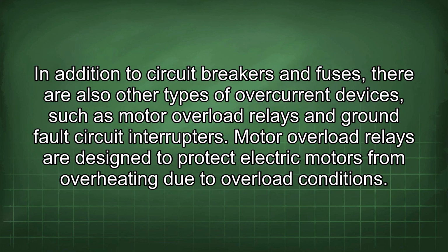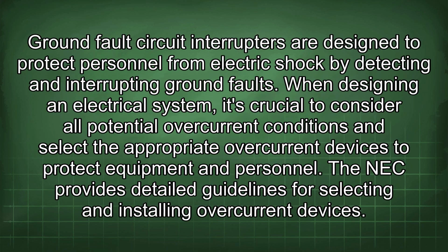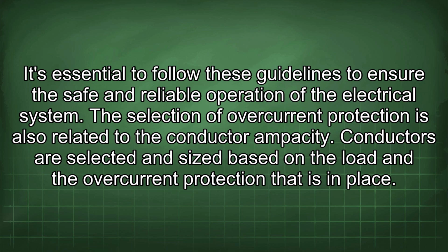In addition to circuit breakers and fuses, there are also other types of overcurrent devices, such as motor overload relays and ground fault circuit interrupters. Motor overload relays are designed to protect electric motors from overheating due to overload conditions. Ground fault circuit interrupters are designed to protect personnel from electric shock by detecting and interrupting ground faults. When designing an electrical system, it's crucial to consider all potential overcurrent conditions and select the appropriate overcurrent devices to protect equipment and personnel. The NEC provides detailed guidelines for selecting and installing overcurrent devices. It's essential to follow these guidelines to ensure the safe and reliable operation of the electrical system.